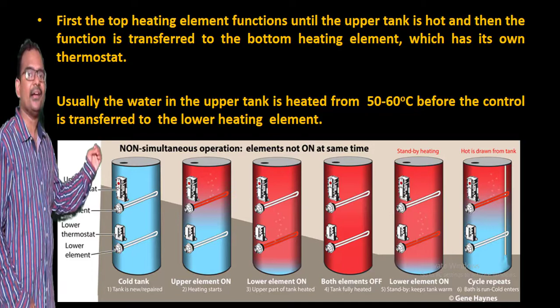As shown in the figure, the geyser consists of two heating elements, an upper heating element and a lower heating element. Initially, the upper heating element is on, heating the upper part of the water to around 50 to 60 degrees, then control is transferred to the lower heating element, which heats the water in the bottom part of the tank, so the complete tank gets heated, and the process repeats.